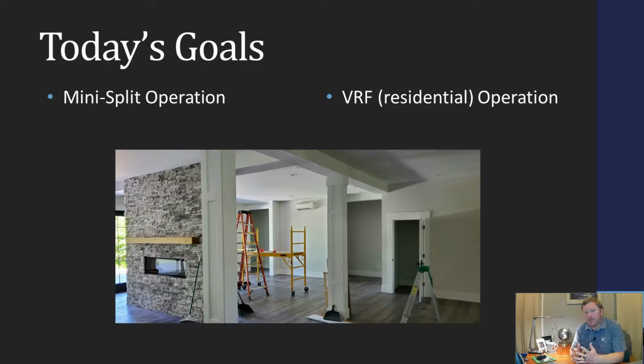So today my goal for you guys is just really understand, how does your mini-split system operate on a daily, regular basis, and then compare that information with, here's all the things the VRF systems can do that the mini-split systems can't do, or here's what the VRF systems do that's better than the mini-split systems. Because as we discussed in the last video, your traditional heat pump is just bare bones heat pump. The mini-split inverter is that entry-level, high-efficient inverter system. And then when you go to the VRF system, that is really the top of the line when it comes to controls and comfort and efficiency and everything else.